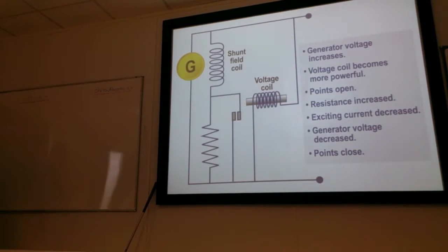This is a slightly different one. This is a vibrating contact regulator. Once again, generator voltage increases, the voltage coil here becomes more powerful. The points will be pulled open, like this relay here, which increases the resistance. That decreases the current through the excitation coil, which decreases the generator voltage, and the points close. Now that's happening 50 to 200 times a second in a vibrating contact voltage regulator. Again, quite efficient, but because of the contact breaker points, the physical points, if you put high loads through them, you burn the points out in no time at all. So they're really only suitable in low current systems.